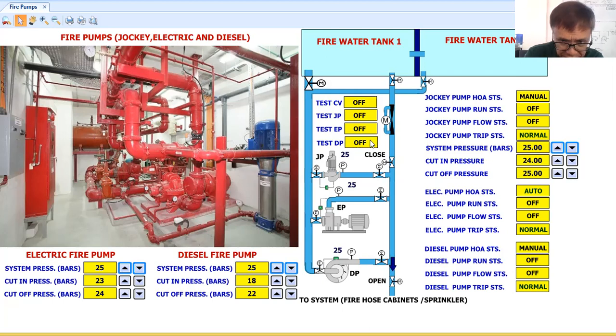Now, the points that I'm monitoring for the jockey pump are the usual points for a pump, okay? So these are the typical monitoring points. As I said, BMS will not be the one to control these pumps. All the BMS will do is just monitor some of the status like hand-off-auto status, run status, pump flow status. Okay, now as you can see here, there is one flow switch installed in the discharge line of the jockey pump. Okay, so this is pump flow status, trip status.